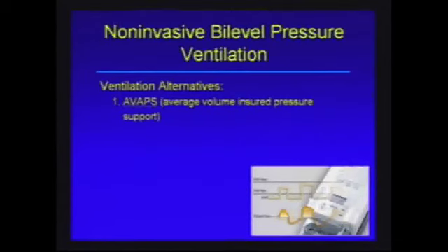On occasion we've had problems with the machine adjusting the IPAP up, and all of a sudden the patient develops mask leak as the higher IPAPs are pushed, and that causes problems because they awaken and don't feel like they're getting their sleep. It's causing them more problems than helping them. So there's a fine line. This is something we always wished we had, and then when we got it, it was one of those be careful what you wish for situations, because it does create some management issues.